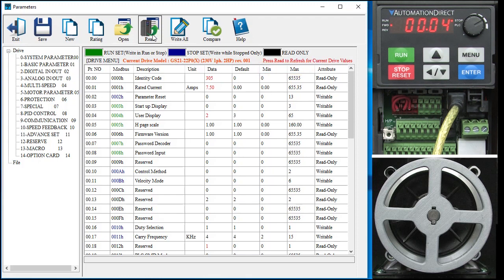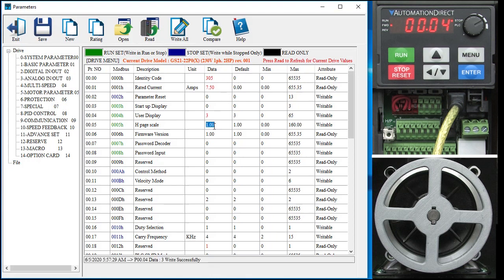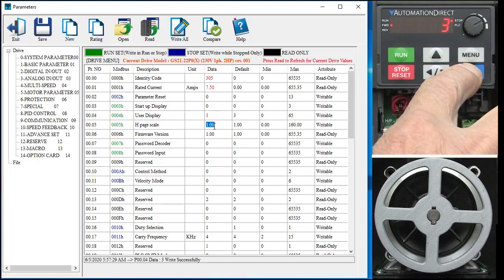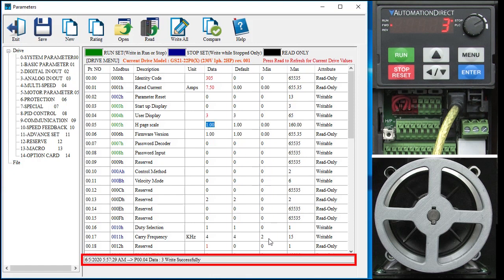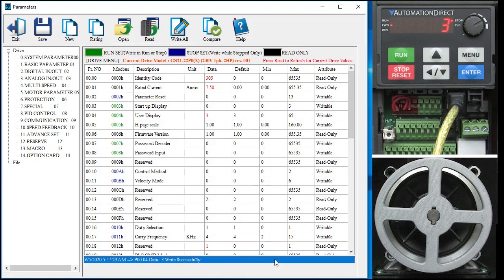Now writes on the other hand happen instantly. For example, let's change that user display back to a 3 and as soon as I hit return or even just click away from that cell, the drive gets updated. And look down here, there is a running log that tells us everything we've done since the last read from the drive. If I do another read, that log gets cleared out.